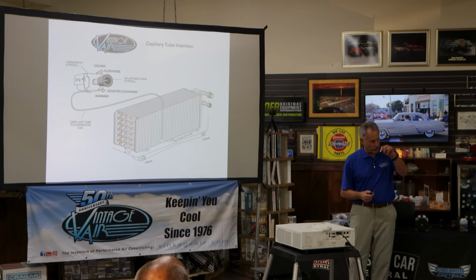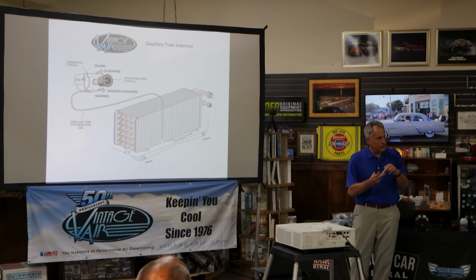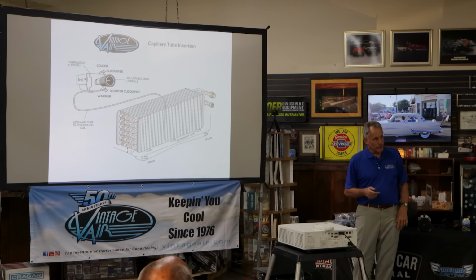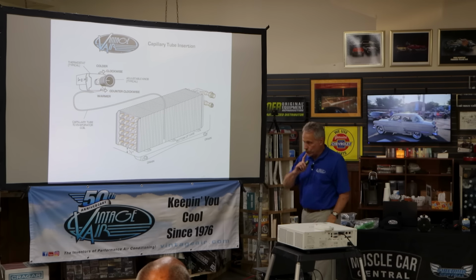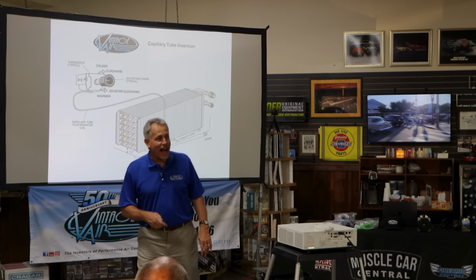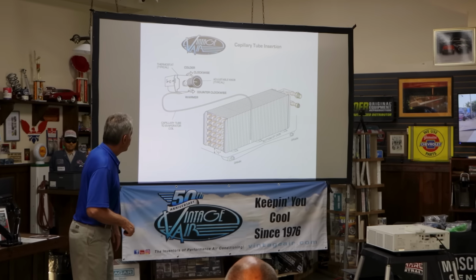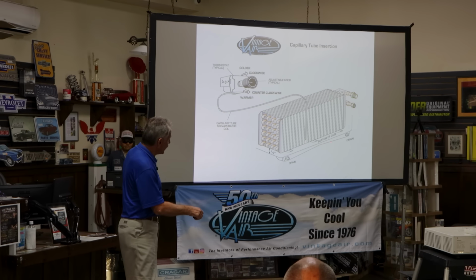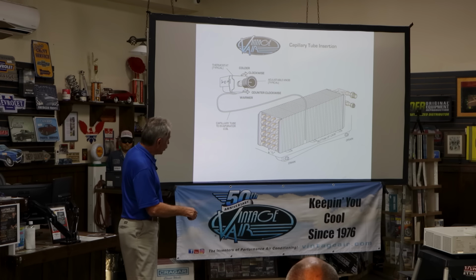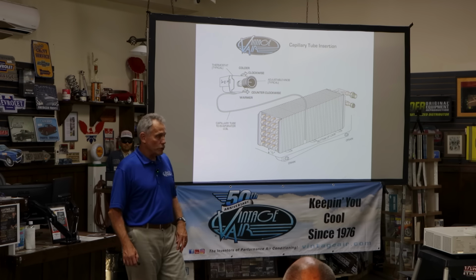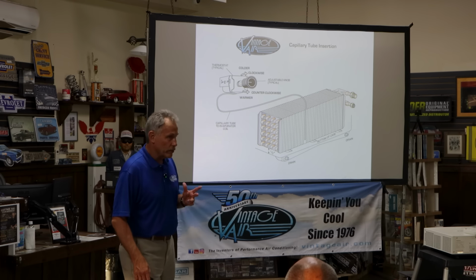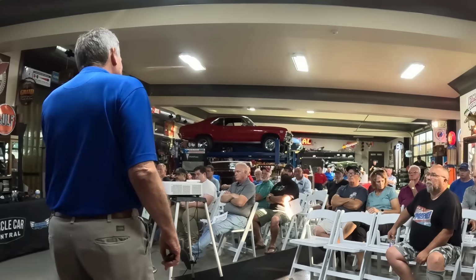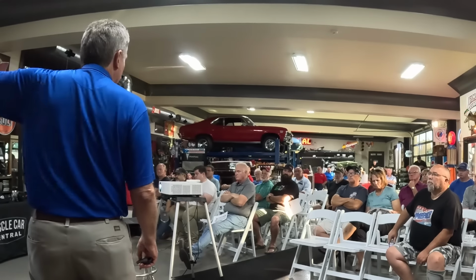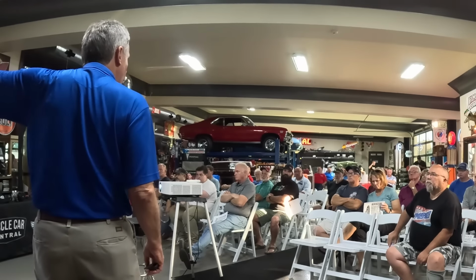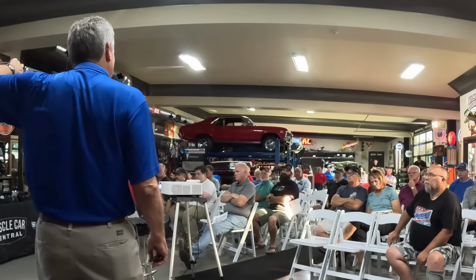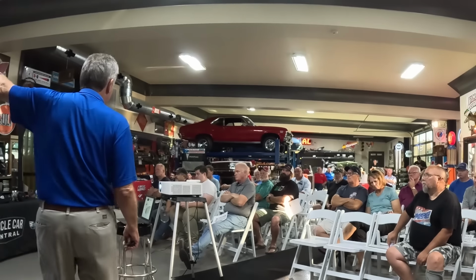So that's something you've got to think about when you're doing that. Just make sure that drain hose falls, it's not plugged, and that your condensate is draining out of there. Because if you don't get the condensate drained out and it just starts building up, one of two things is going to happen: it's either going to freeze or it's going to block the air. You can't blow through water really well. It blocks the air trying to flow through the coil, and you're not removing heat from it.